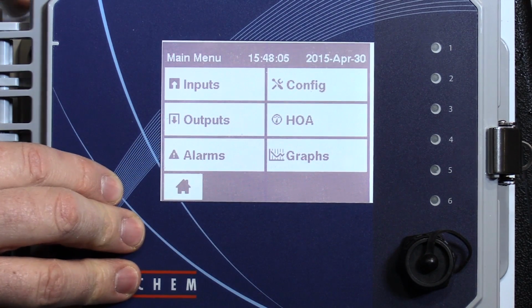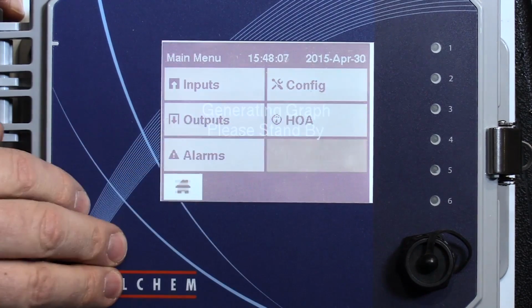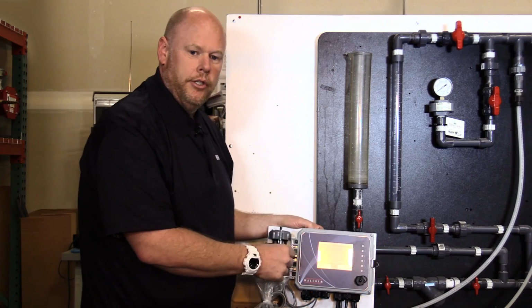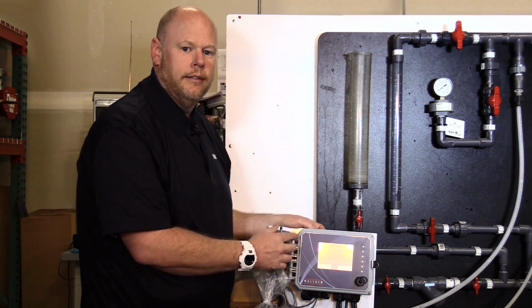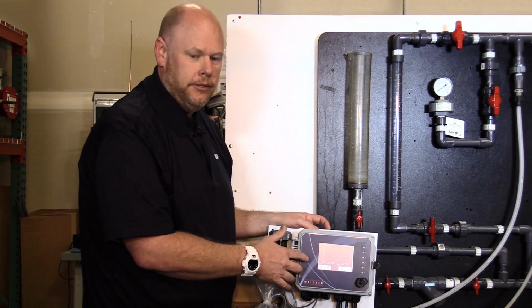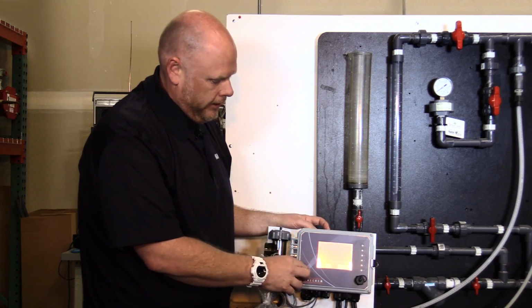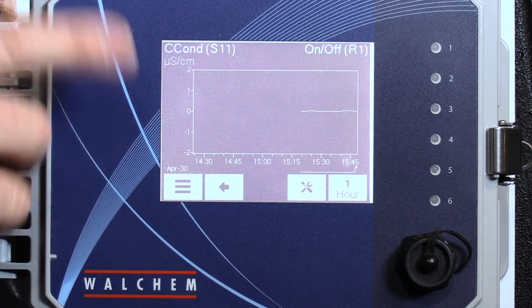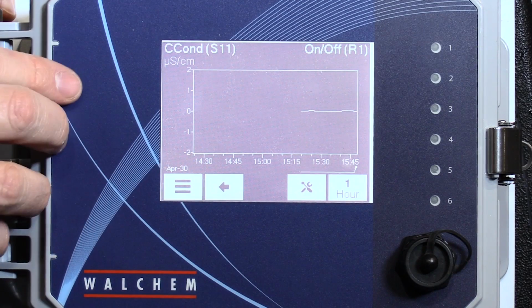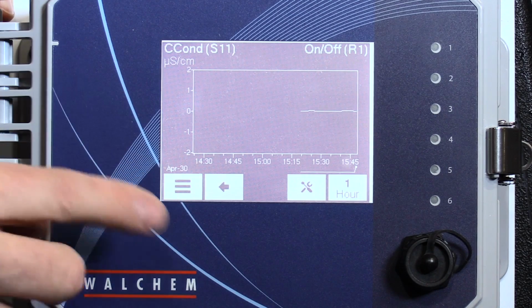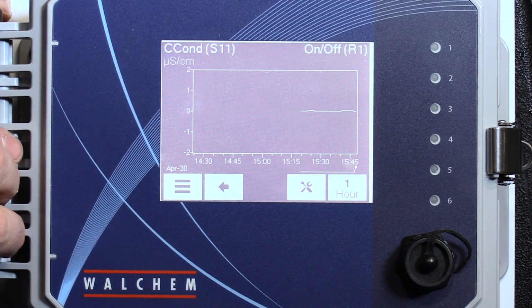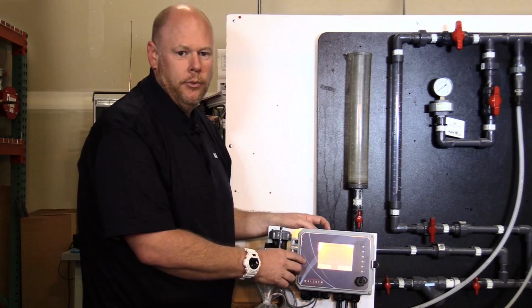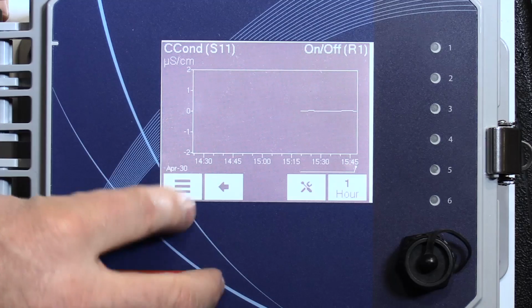The control also has online graphing, which will show you the last hour, last day, last week, and last month, all across the screen. You can select the flow switch and the conductivity. And if you have a water meter, you can select those and you can graph those all online, which can be exported to a USB flash drive.